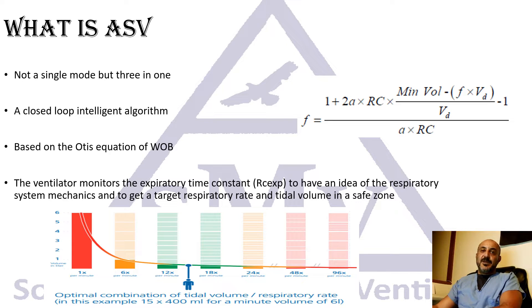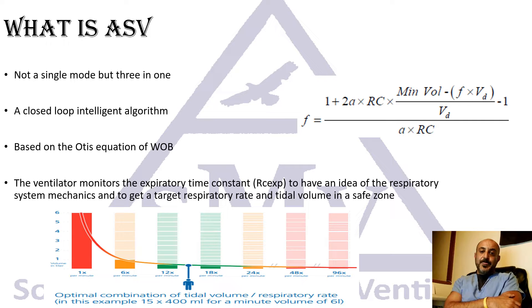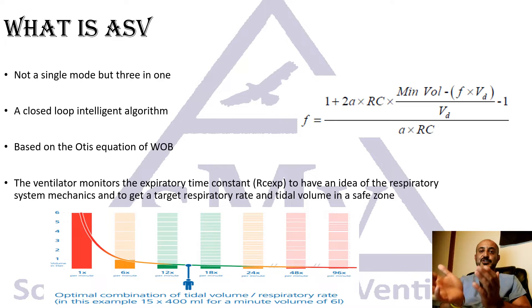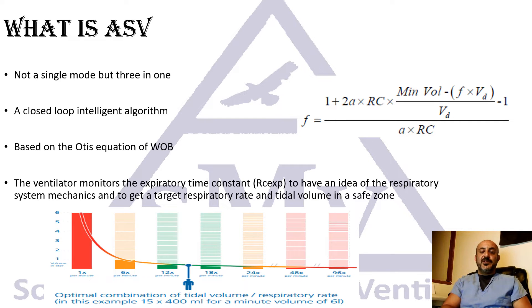What is ASV? ASV is really not a single mode — it's mainly an algorithm, a closed loop, and one of the intelligent modes of mechanical ventilation. If the patient is passive with no spontaneous effort, ASV is basically a pressure-controlled continuous mandatory ventilation mode. If the patient and the ventilator are sharing work, it becomes a pressure-controlled intermittent mandatory mode. And if the patient is fully spontaneous and triggering, it becomes pressure support ventilation.